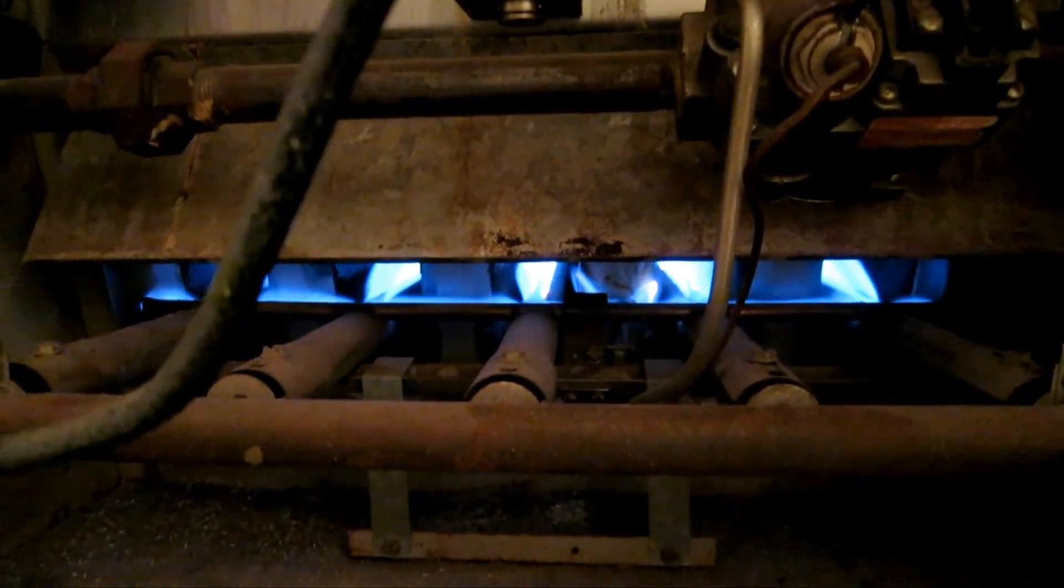Of course there's a reason why the flame rollout switch triggered. It's there for a safety reason. When the burners are dirty or when there's not enough ventilation, and when there's not good ventilation, then the flames from the burner will roll out and trigger that switch. So again, that switch is there for a safety reason.